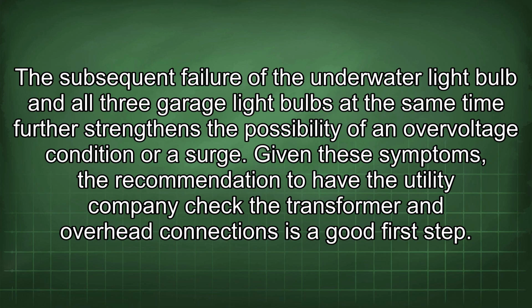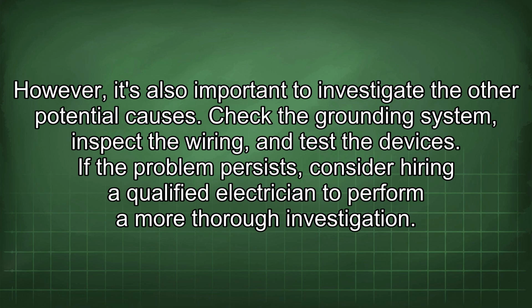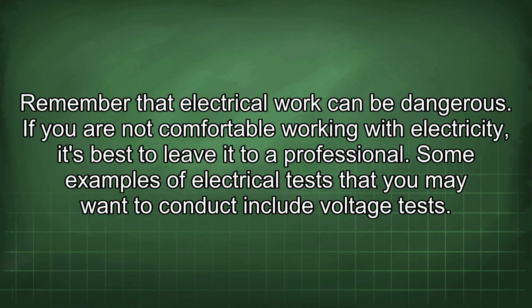Given these symptoms, the recommendation to have the utility company check the transformer and overhead connections is a good first step. However, it's also important to investigate the other potential causes. Check the grounding system, inspect the wiring, and test the devices. If the problem persists, consider hiring a qualified electrician to perform a more thorough investigation. Remember that electrical work can be dangerous. If you are not comfortable working with electricity, it's best to leave it to a professional.